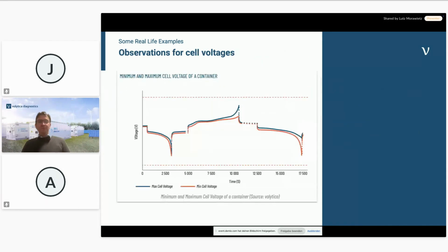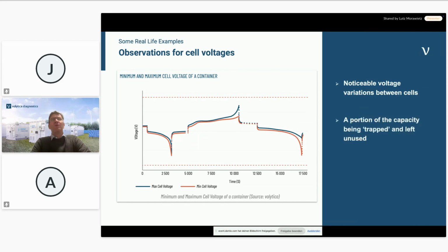Another thing we found here is a very detailed plot where we looked at the maximum and minimum voltage inside of a container, which gives us an indication of how balanced or aligned the cells are. As you can see, this is not very well aligned - the highest voltage is always significantly above the lowest voltage. In a perfectly aligned battery, we'd expect both lines to be exactly on top of each other.